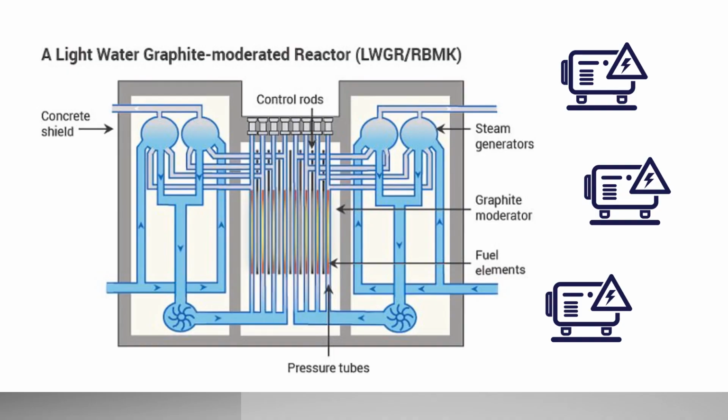Even after a nuclear reactor is shut down, whether accidental or purposeful, it still continues to generate heat. Not as much so, but it's still enough to require coolant to be pumped around the core. In the event that power is lost, Chernobyl had 3 backup generators which could reach full load within 90 seconds.